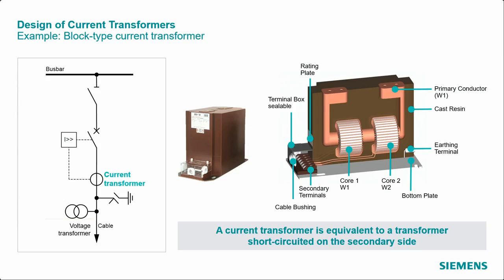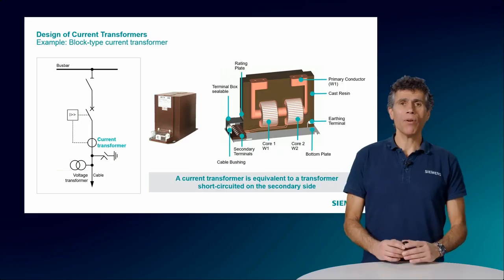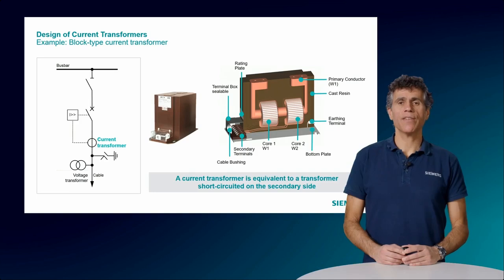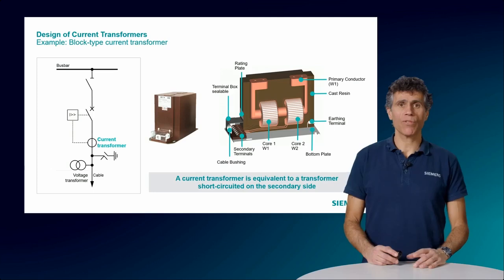From there, they are wired to the low voltage box through the cable bushing, and they are connected to the relevant devices that analyze the signal. Because the block CT can't be opened, its characteristics are written on a rating plate placed on its outside. This component provides vital information about the transformer, such as its current and voltage ratings, number of cores, frequency, and other manufacturer details. It helps in ensuring the correct application and management of a transformer throughout its life cycle. The core of a block CT is equivalent to a transformer short circuit on the secondary side.